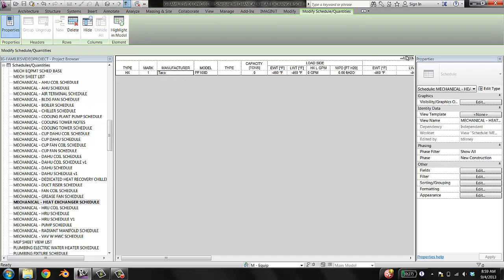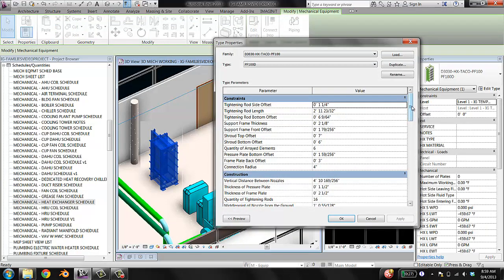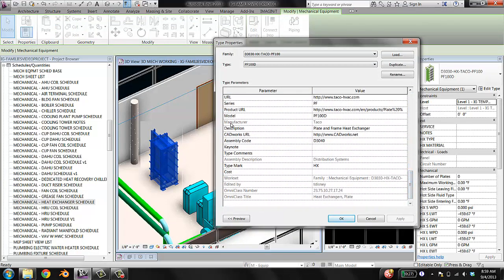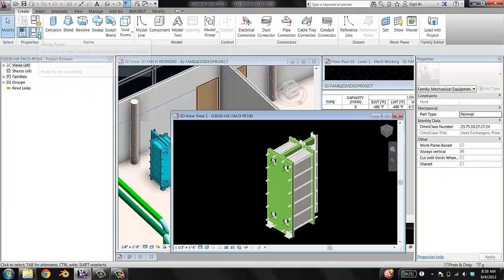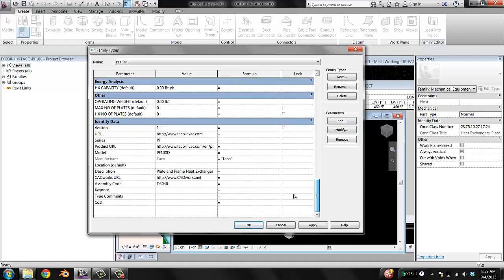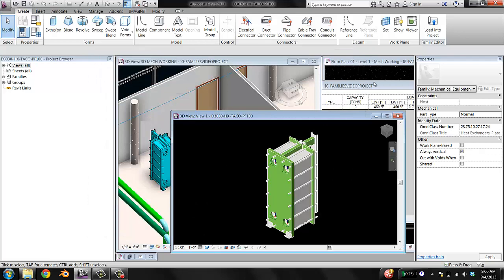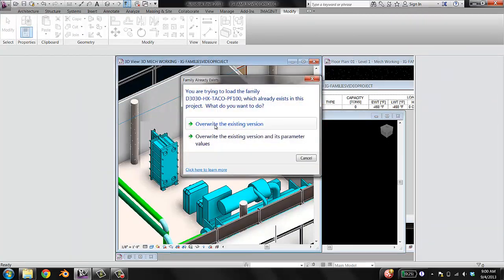I can't edit the Manufacturer field and I want to know why. Going back to my family and hitting Edit Type, I can see that the manufacturer parameter is grayed out. That typically means it's locked. The model here is not locked — I can edit it — but the manufacturer is locked. It's fine that it says TACO; I just want it to be all caps. So I'll edit my family, go into Family Types, find Manufacturer, and I see it's been locked to a formula. I'll delete that, change it to TACO, hit OK, load into the project, and overwrite the existing version.